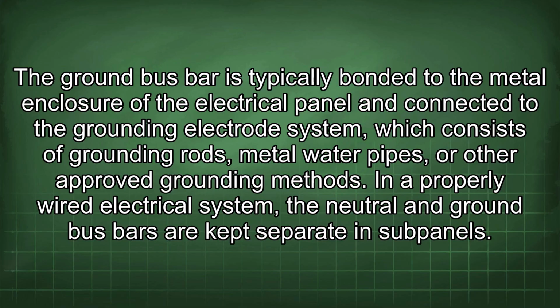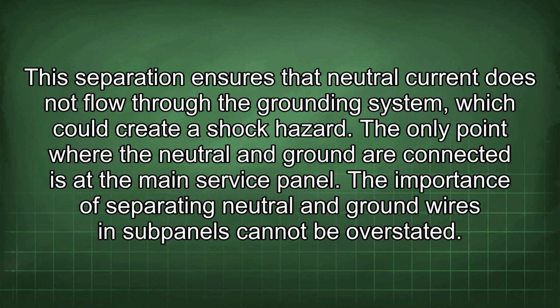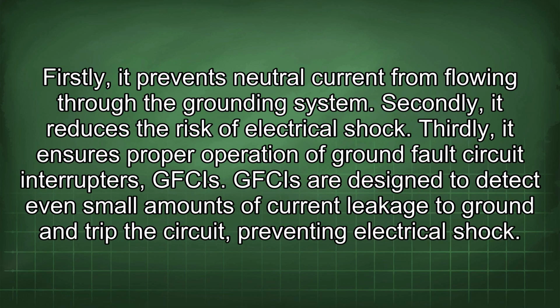In a properly wired electrical system, the neutral and ground bus bars are kept separate in subpanels. This separation ensures that neutral current does not flow through the grounding system, which could create a shock hazard. The only point where the neutral and ground are connected is at the main service panel. The importance of separating neutral and ground wires in subpanels cannot be overstated. Firstly, it prevents neutral current from flowing through the grounding system. Secondly, it reduces the risk of electrical shock.